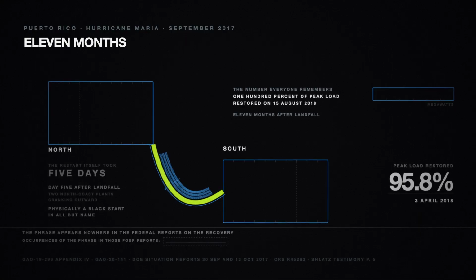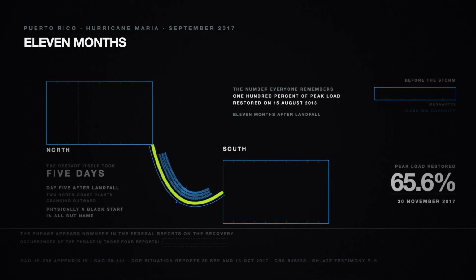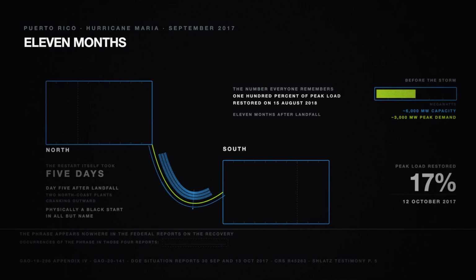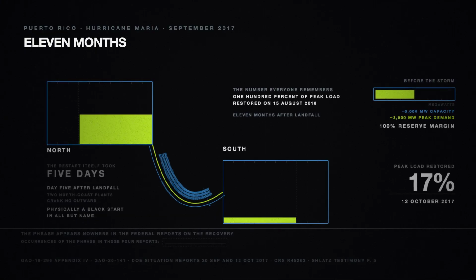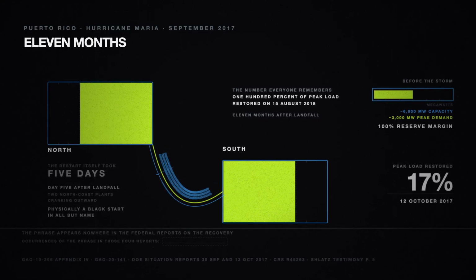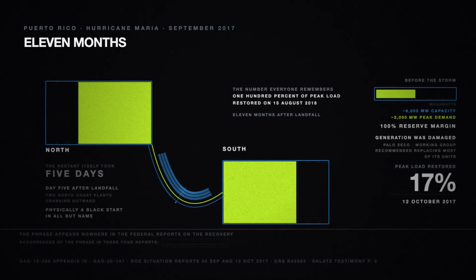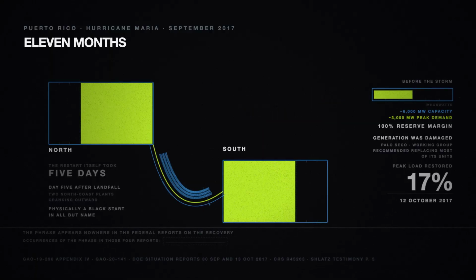So why 11 months? Not generation. Before the storm, the island had about 6,000 megawatts of capacity against a peak demand of about 3,000, 100% reserve margin. Generation was damaged. Palo Seco badly enough that the working group recommended replacing most of its units. But generation was never the binding constraint.